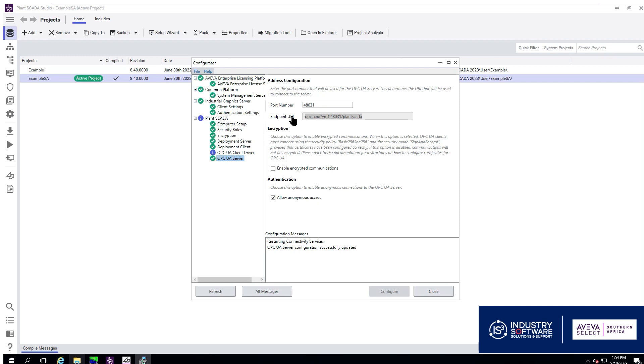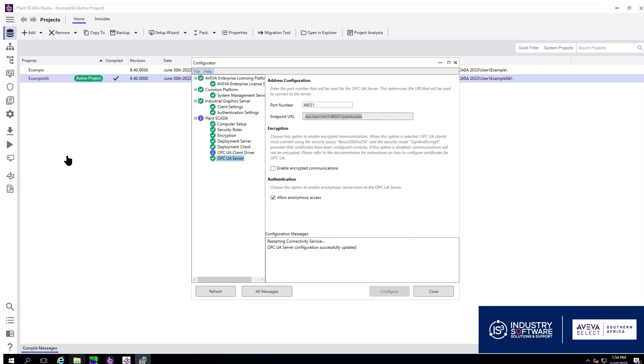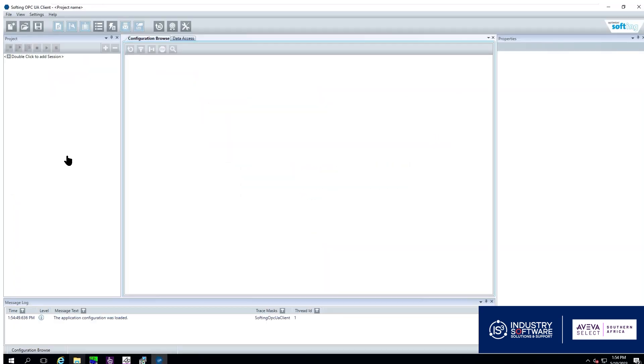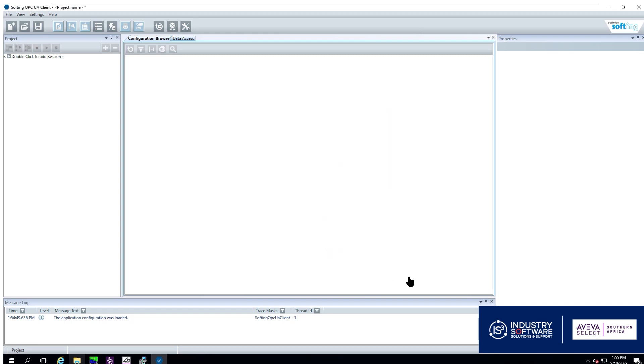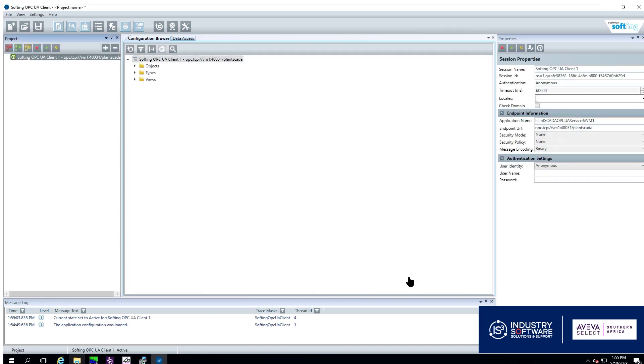Once it is configured we can open up our OPC UA client we will be using to read this data. We click to add a session, input endpoint URL, validate our connection and wait for it to give us a green light. We click OK and we can now add our session and see what is there.